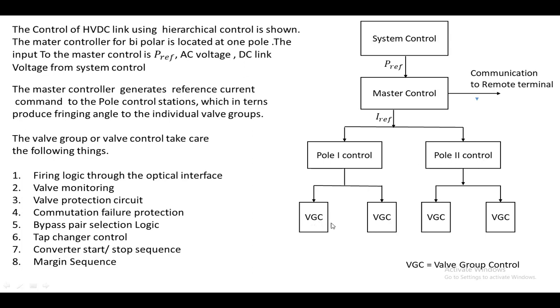Under the pole-1 control, there is VGC-1 and VGC-2 — VGC stands for valve group control. The master control requires some information to generate a current reference: first is the P-reference, which is how much real power we have to transmit on the DC link; next are the reference AC voltage and reference DC voltage. These are supplied by system control to master control. The master control generates the I-reference to both pole stations, which then issue firing angle commands to the group of valves in station-1 and station-2.